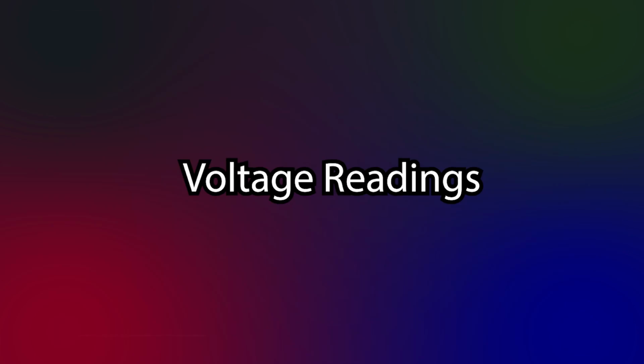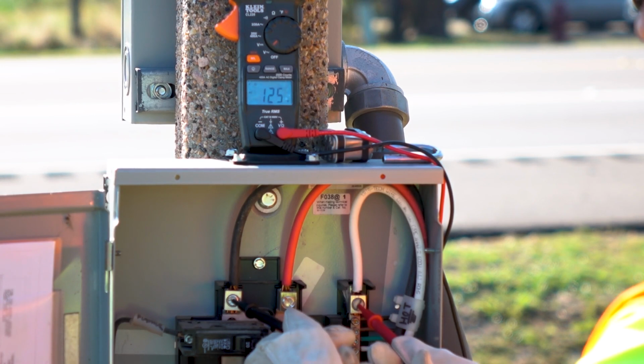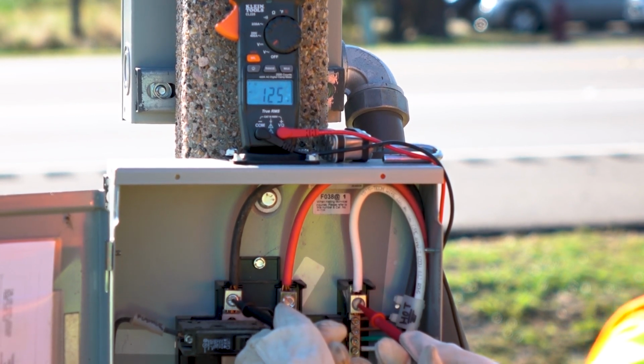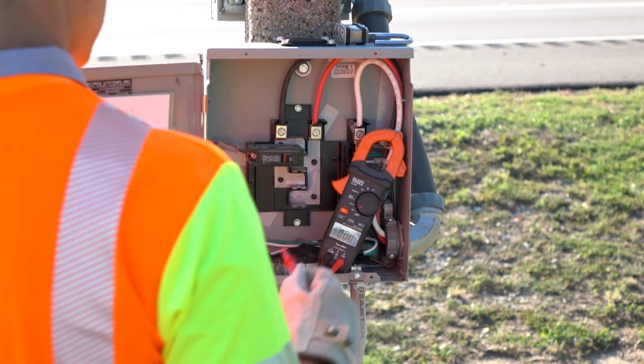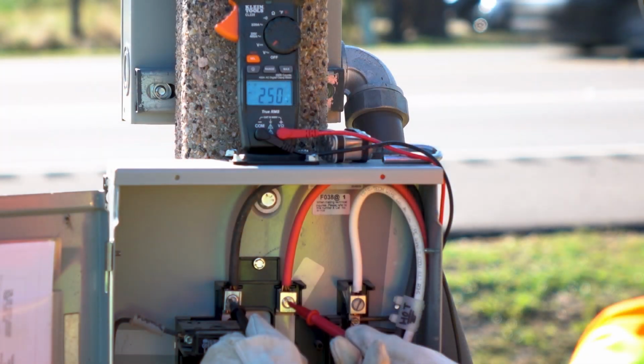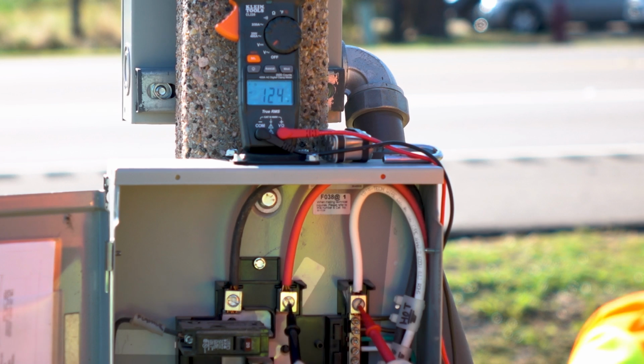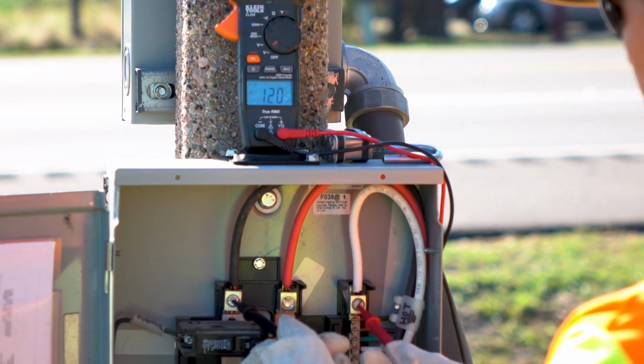Now, let's move on to voltage readings. Before power is applied to any electrical equipment, the following voltage measurements should be taken at the service by the contractor and recorded in the presence of either the project's engineer or inspector. Reading number 1, line 1 to line 2. For a 120-240 volt system, the voltage check should show approximately 240 volts. Reading number 2, line 1 to the neutral or ground. This reading should be approximately 120 volts, or 1/2 of the previous reading. Reading number 3, line 2 to the neutral or ground. This reading should be the same as line number 1 to the neutral or ground.